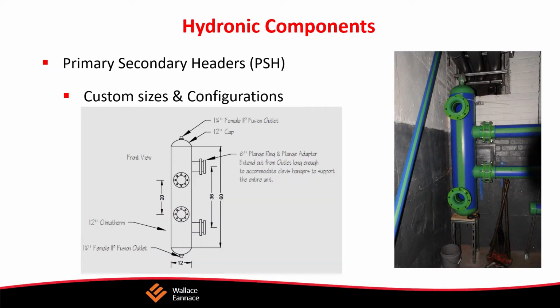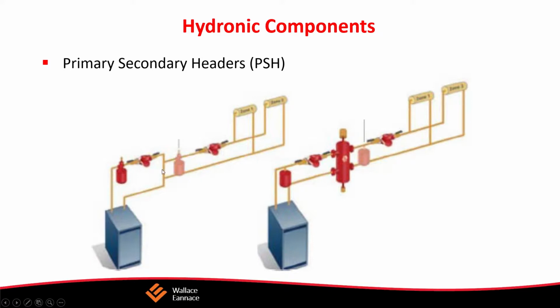And the next really important device on a hydronic component is going to be to eliminate air. If you've never noticed, when you take a bottle of soda out of the refrigerator and it's cold and you open it, none of the air comes out. When the bottle of soda is warm and you open it up, it usually wants to overflow. So whenever you heat water up, the air has a tendency to want to escape. There's always air inside the system, and it has a tendency to want to escape. So controlling the air is critical to hydronic systems.